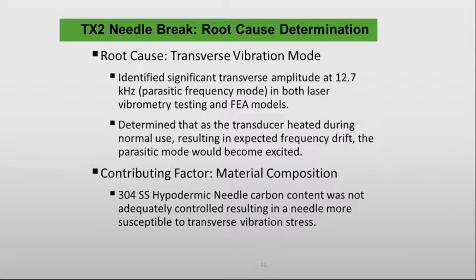The third thing, which was very serendipitous to be honest, is we found that in the course of all the investigations we were doing, even though we had the same specs to our suppliers, there was a supplier that provided a needle that seemed not to break as much. And this is before we put the last two changes I mentioned into effect, the design change and the side-to-side manufacturing process change. We found probably a 50% reduction in fractures by just going to a different vendor. And that had to do with the carbon content of the stainless steel. They both satisfied the design criteria, or the manufacturing specs, but they were actually different in fact. So for your information, the simplest thing to understand for the reps that are on the phone and also for the clinicians is we made three changes.